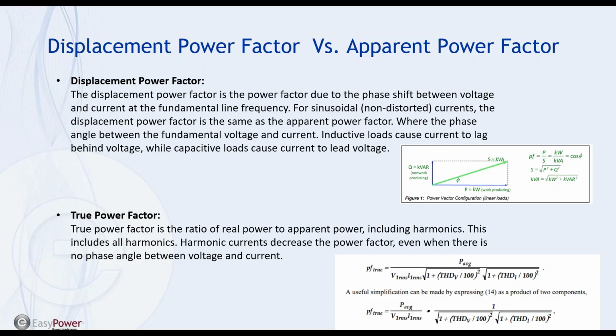Displacement power factor is associated with the fundamental 60 hertz or 50 hertz power factor. It is the phase angle shift between voltage and current. It's the amount of reactive power as measured at 60 or 50 hertz, or the fundamental frequency, that is of concern. And to my knowledge, it is also the primary component of what is penalized by the utility. When the electric utility is talking about power factor, they are talking about displacement power factor. It has nothing to do with harmonics.